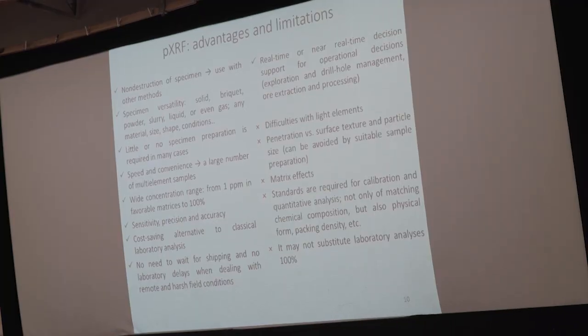Let's sum up advantages, and I wouldn't call them disadvantages, but limitations of PXRF. It's a non-destructive method to analyze various samples from solids to liquids in versatile size, shape, and conditions. It requires little to no sample preparation. It is fast, convenient, and under certain conditions, sensitive, precise, and accurate. Unlike most of the element analysis techniques, it allows a wide concentration range detection, from 1 ppm to 100%.